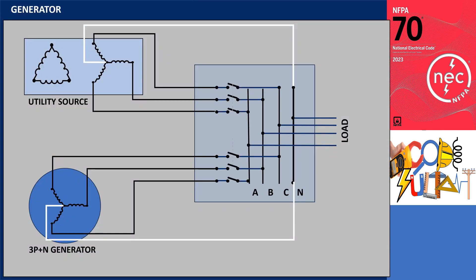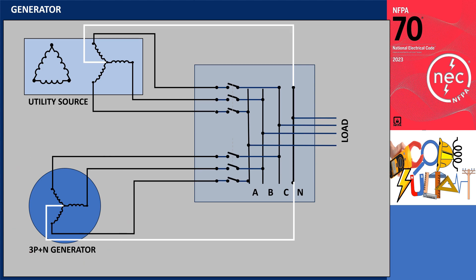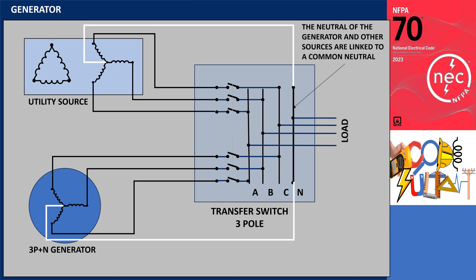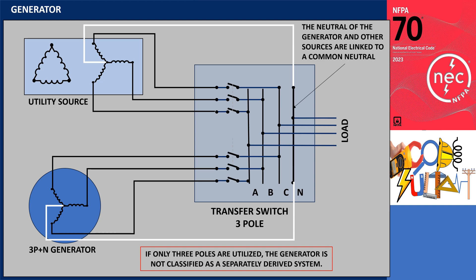In the case of a generator configured with three poles plus neutral, if the transfer switch utilized comprises only three poles, the neutral of the generator and other sources are linked to a common neutral. The neutral conductor is firmly interconnected to a grounded neutral conductor supplied by the service system. Therefore, to determine whether such a generator constitutes a separately derived system, it depends on the number of poles employed in the transfer switch.